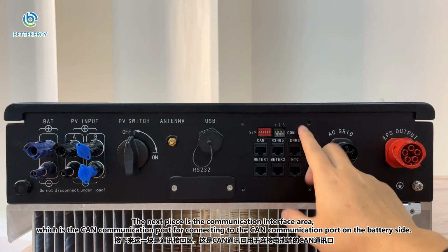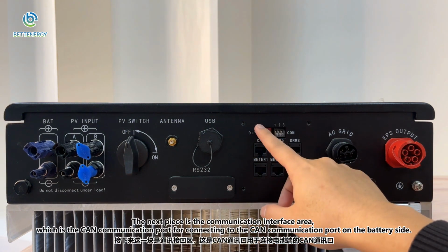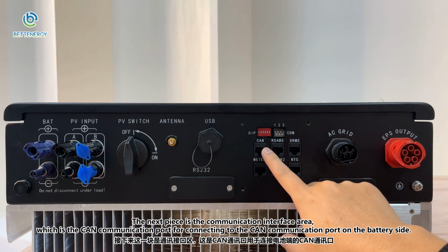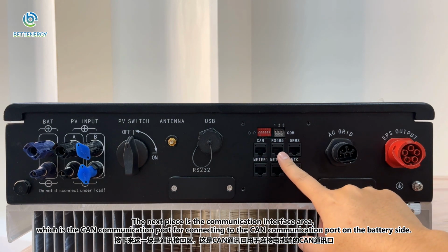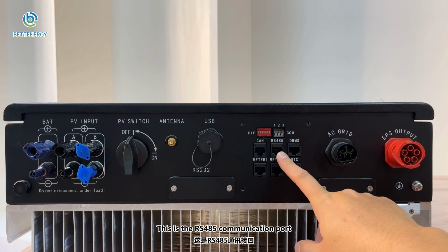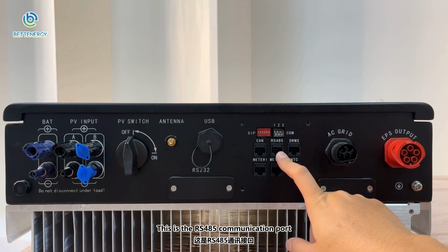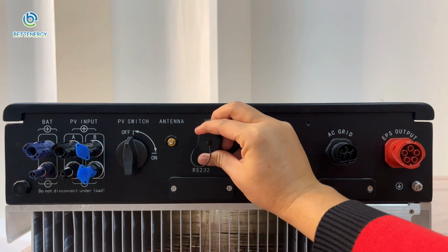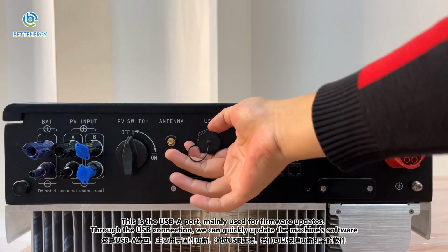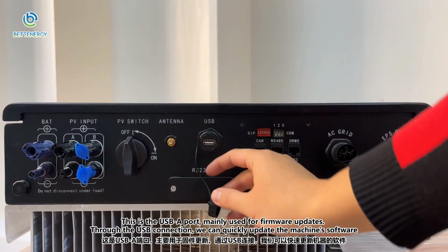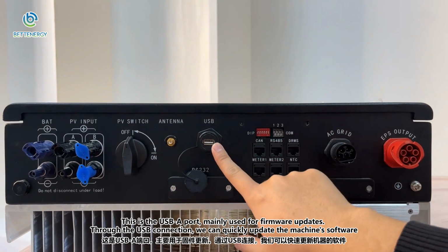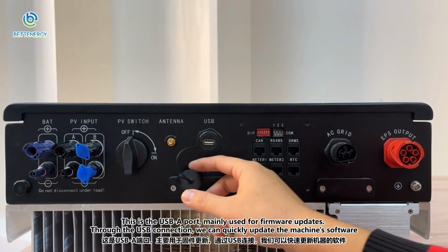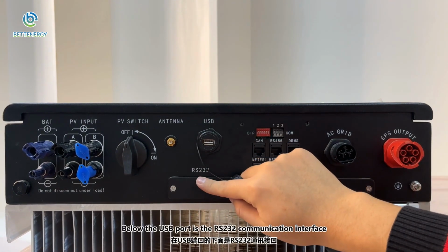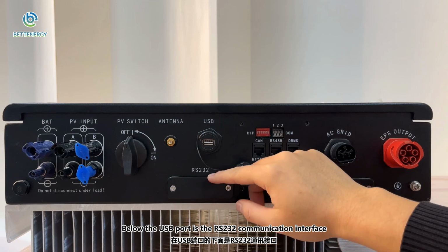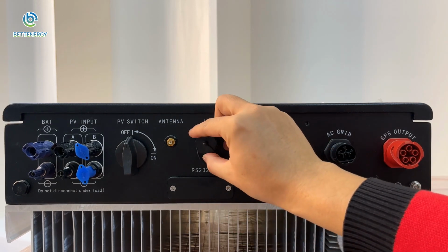The next piece is the communication interface area, which is the CAN communication port for connecting to the CAN communication port on the battery side. This is the RS485 communication port. This is the USB-A port, mainly used for firmware updates. Through the USB connection, we can quickly update the machine's software. Below the USB port is the RS232 communication interface.